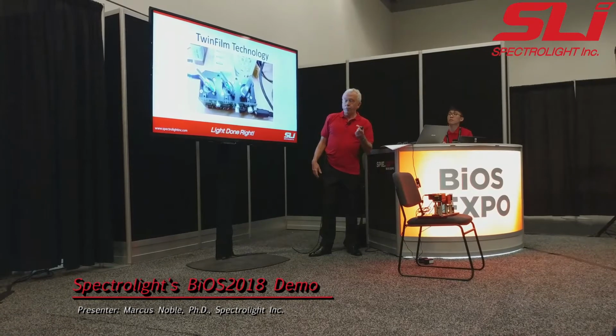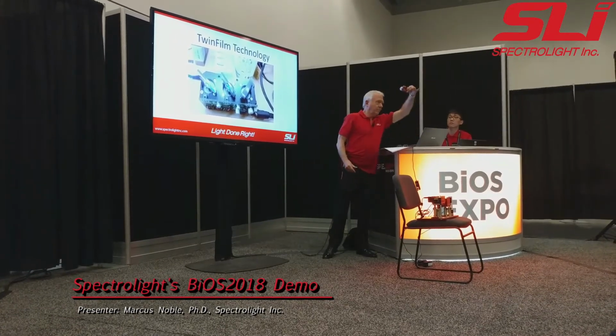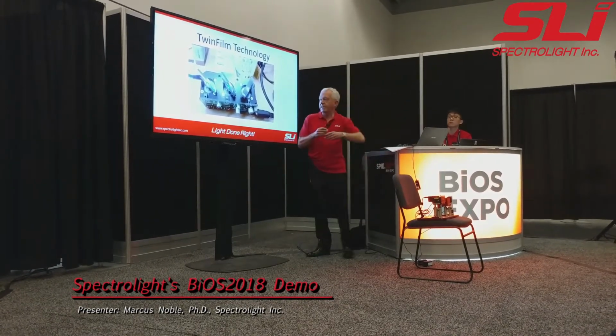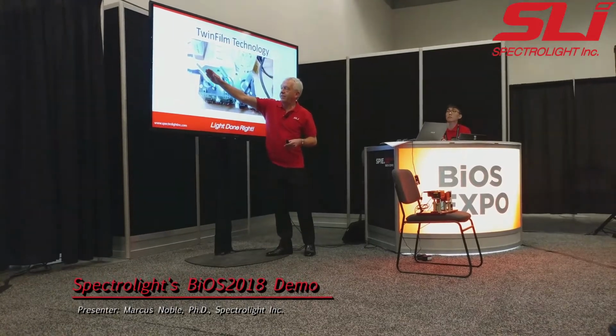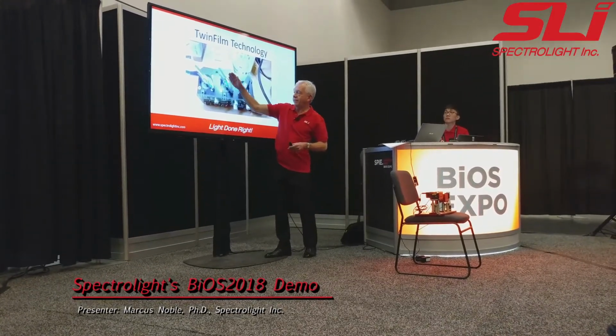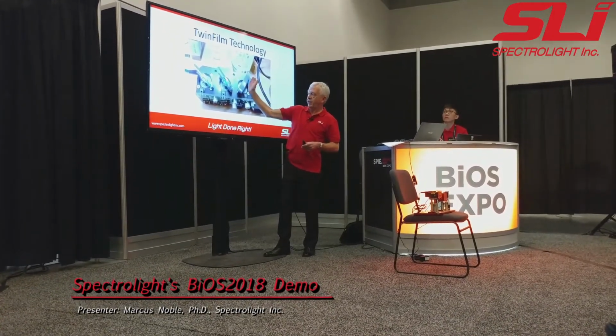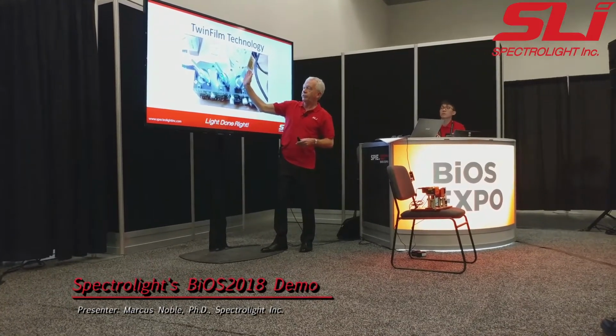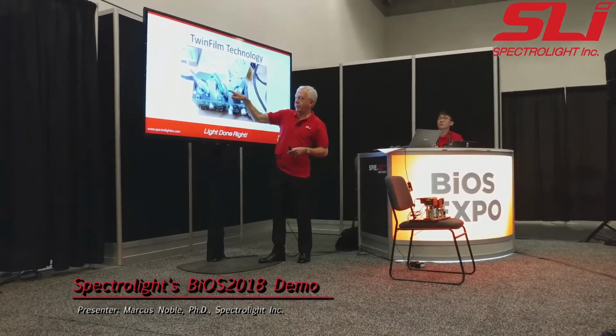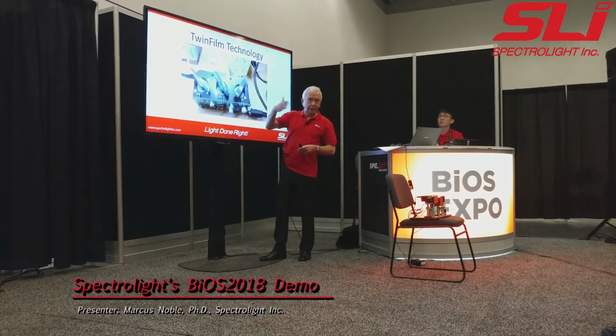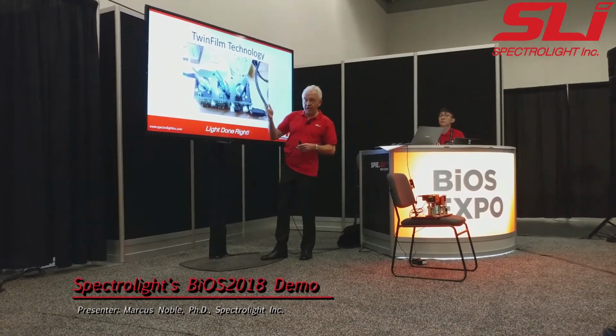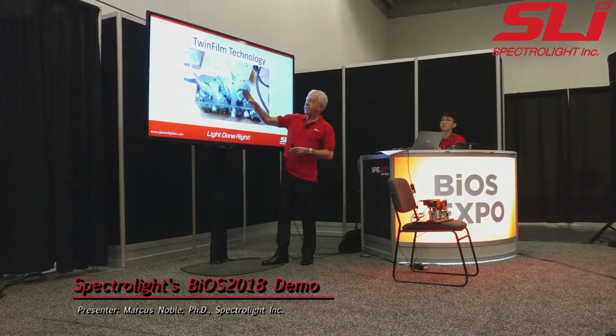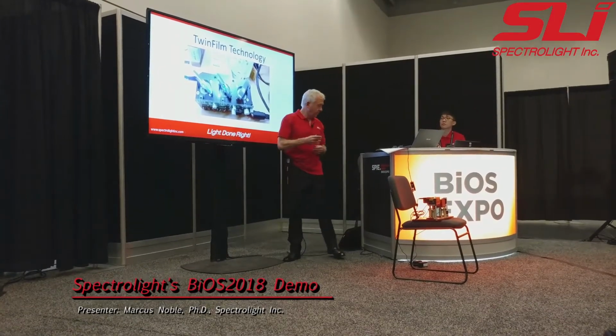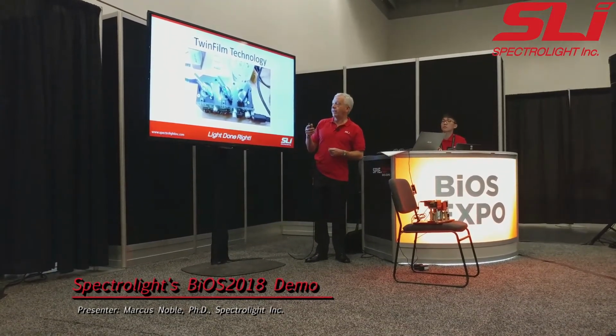Here's a photo of one of these with the cover off. You can see first filter, second filter, the offset plate. They're all direct drive, micro-stepping little stepper motors. So there's no play, no backlash, no loss of calibration. So once the device is calibrated, you know exactly where the wavelength is.